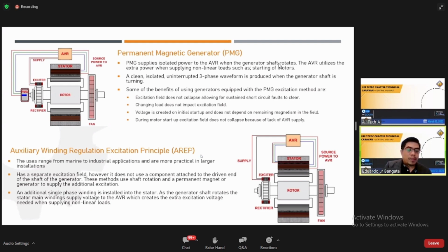Okay, the uses range from marine or industrial applications and are more practical in larger installations. As a separate excitation field, however, it does not use a component attached to the drive end of the shaft of the generator. These methods use shaft rotation and a permanent magnet generator to supply the additional excitation.